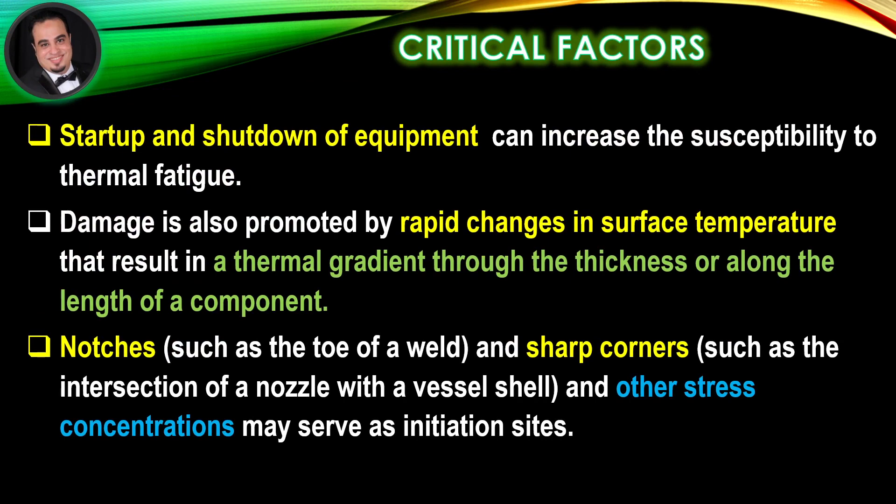Startup and shutdown of equipment can increase the susceptibility to thermal fatigue. Damage is also promoted by rapid changes in surface temperature that result in a thermal gradient through the thickness or along the length of a component. Notches such as the toe of a weld, sharp corners such as the intersection of a nozzle with a vessel shell, and other stress concentrations may serve as initiation sites.